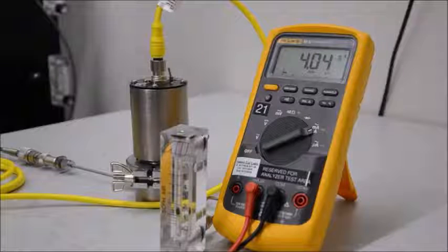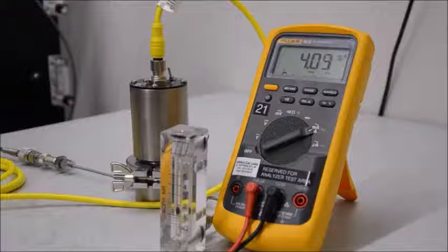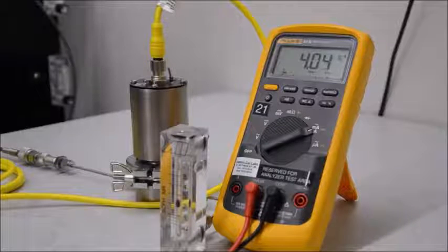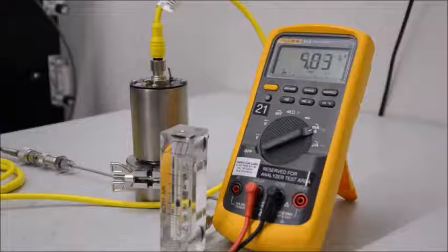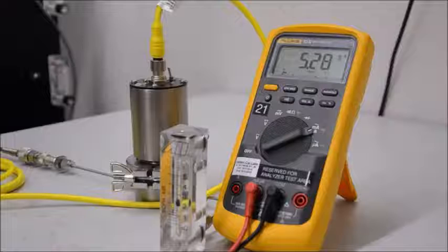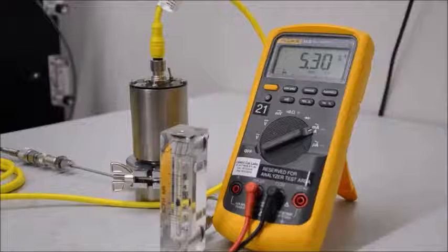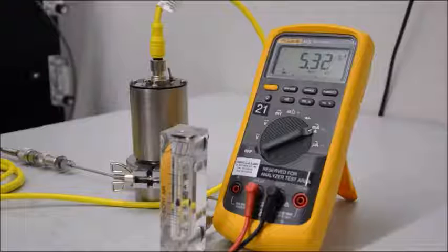Now we're going to check our air calibration with our span gas. Our span gas value is 83 ppm. Once we switch to the span gas, the response should be very fast. We'll switch it now. The multimeter is going to go up to around 5.34 milliamps. That equates to 83 ppm. This will take a couple minutes for the sensor to settle.